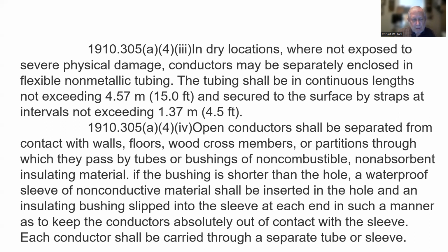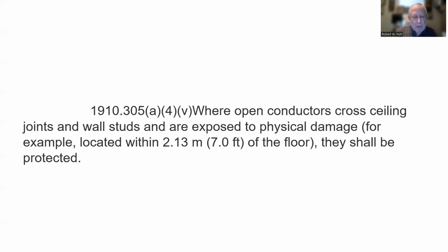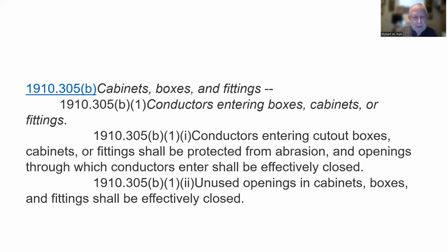Open conductors separated from contact with walls, floors, wood cross members, or partitions through which they pass. So open conductors is something that's not really good to get into. Where open conductors cross ceiling joists and studs. All right, cabinets, boxes, and fittings. Conductors entering boxes, cabinets, or fittings. Conductors entering cutout boxes, cabinets, or fittings shall be protected from abrasion, and openings through which conductors enter shall be effectively closed.